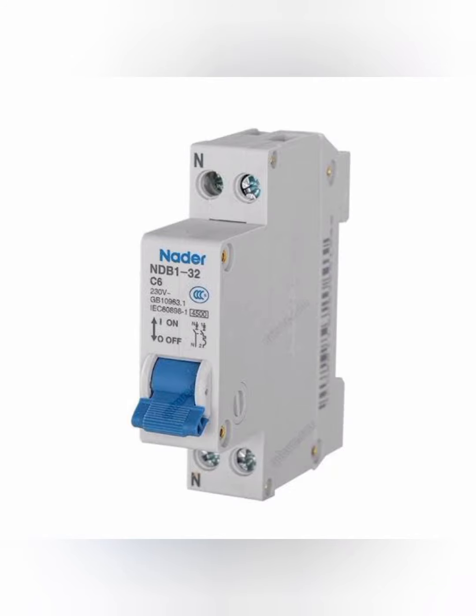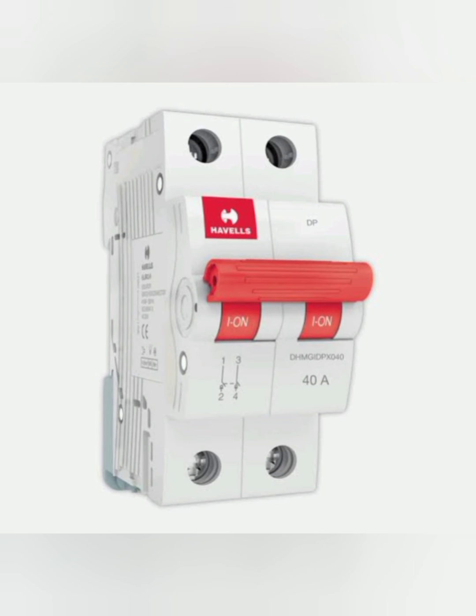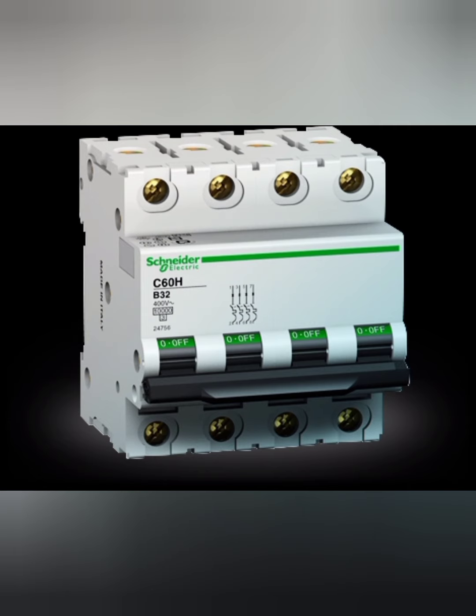Next, these are some examples of MCBs. This is a single pole MCB. Here it is marked as C type, 6 amps, 220 230-volt supply. So it is a single pole. Then this is a double pole. It is a 40 amps MCB. Here we have two separate single poles, which means we can connect two cables here. That's why it is called a double pole MCB. This is a 4-pole MCB. Here we can easily connect the three phase cables and also the neutral cable, and this is marked as B32. B32 means B type MCB. As we saw, B type MCB has 3 to 5 times its rated current for instantaneous tripping, and the 32 marked on the side is the rated current of this 4-pole MCB.